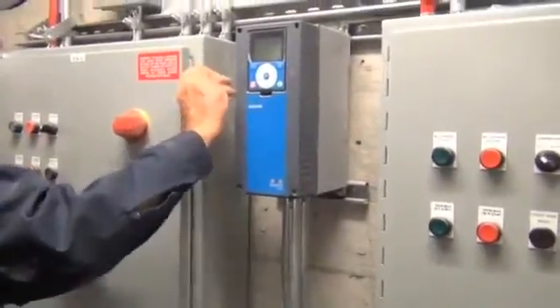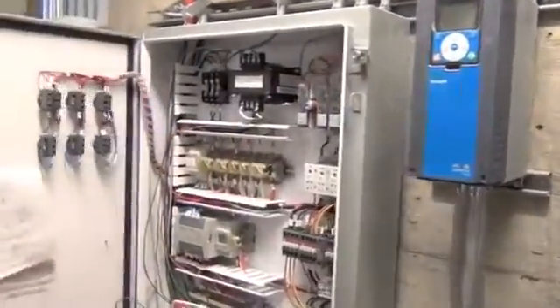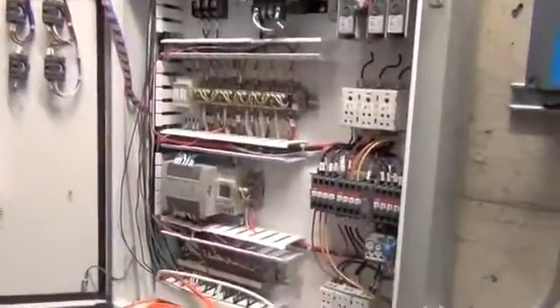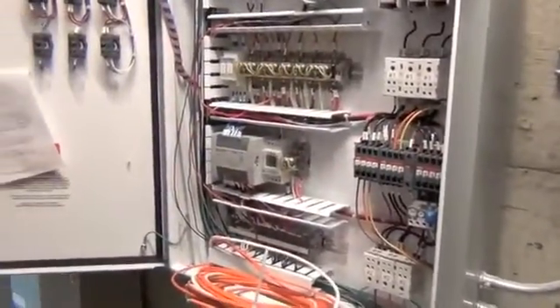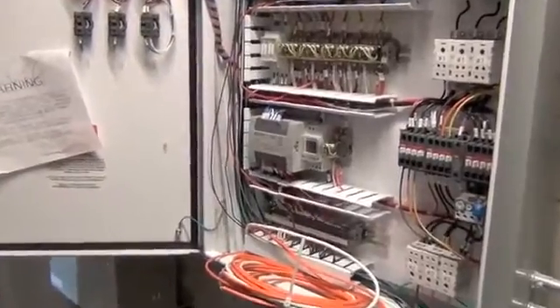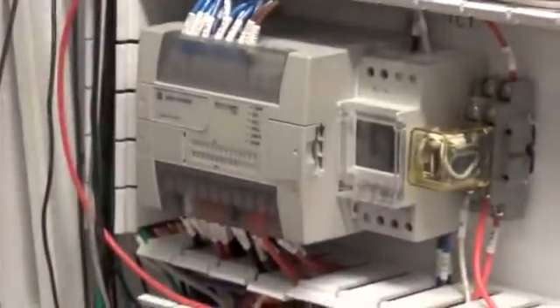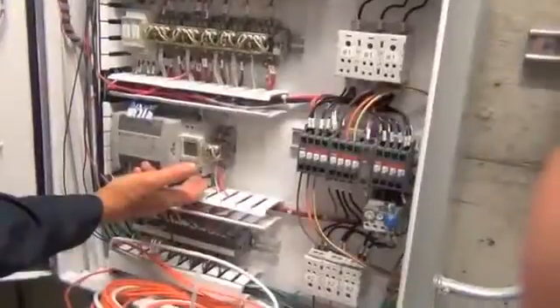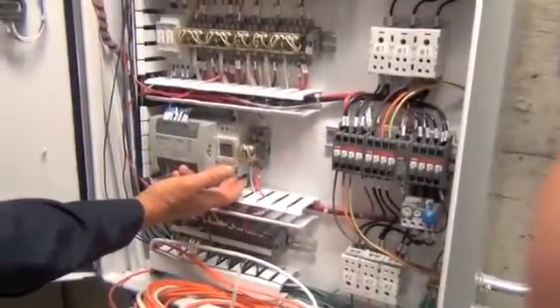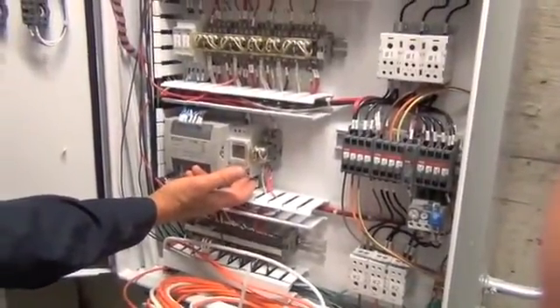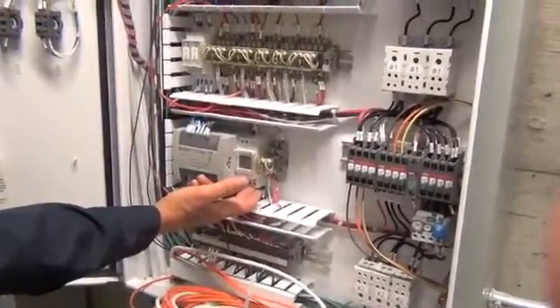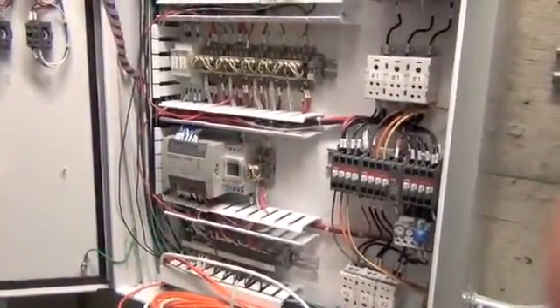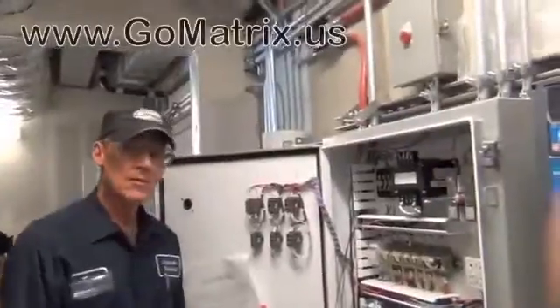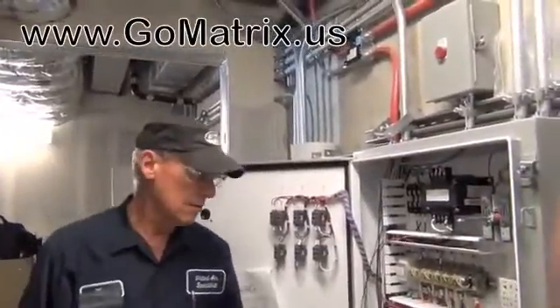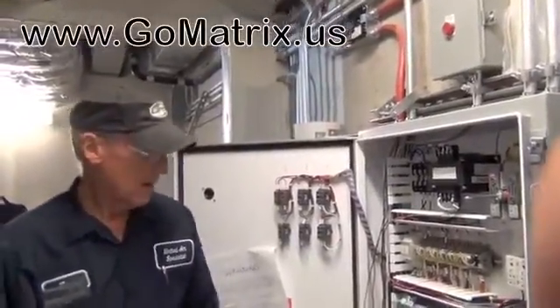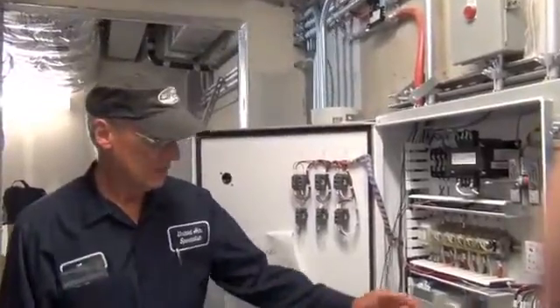Inside the heart of the system we have a PLC. The PLC is, we call it a computer, operates the system as far as start-stop, wash cycle, power pack failure. This is a time clock. The time clock is set as far as a program time, and that's determined by the customer. And that operates the wash cycle every day. The PLC not only operates the heart of the system, but we also have a fire protection system that's linked to the PLC.